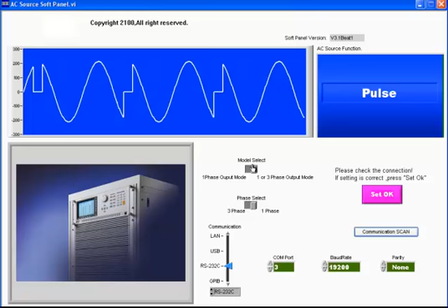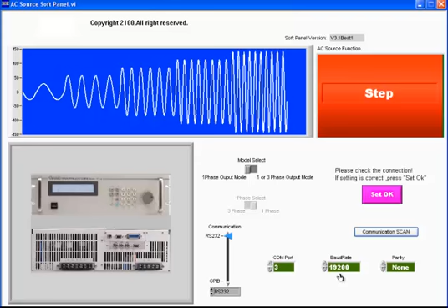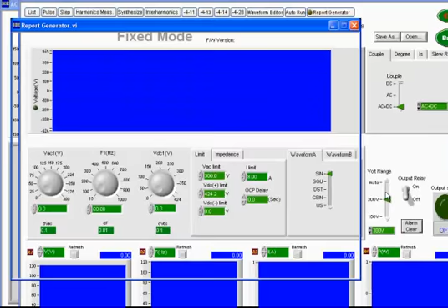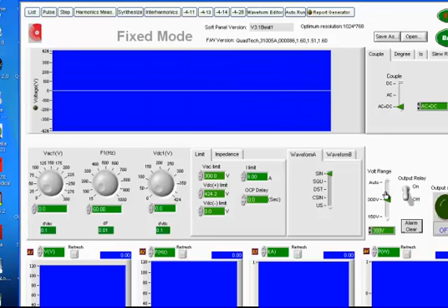We can either have communications via RS-232 or GPIB. In this particular case, we are connected to RS-232, COM port 3 at 19200 baud. We click on OK. Brings us to the basic menu. From this menu, we can control the voltage of the AC source dynamically, the frequency, and any DC level. So we can basically shift the AC signal up or down.